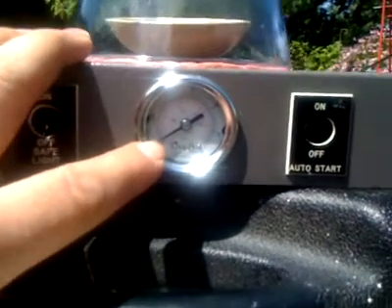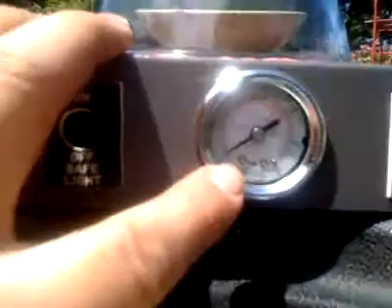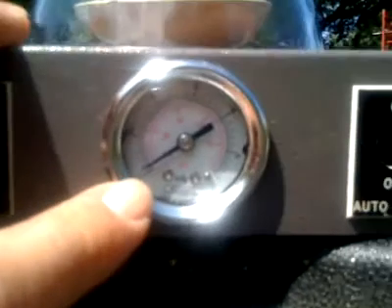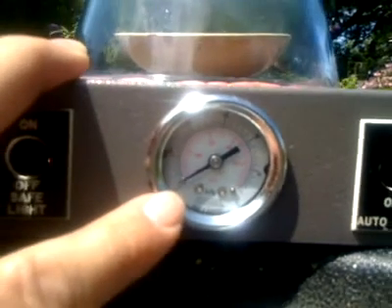And then all of a sudden I hadn't noticed that this second stage, further down the chain, had stopped. I heard it click and shake a little bit as it started up again, and then suddenly the pressure has dropped to — again, I'm treating this gauge as accurate — but I read that as 29.5 at the moment. 29.5 inches mercury.